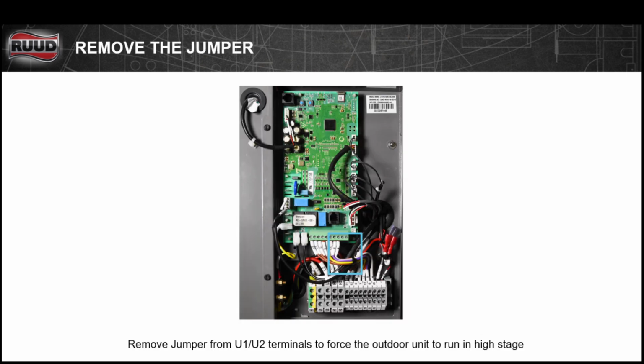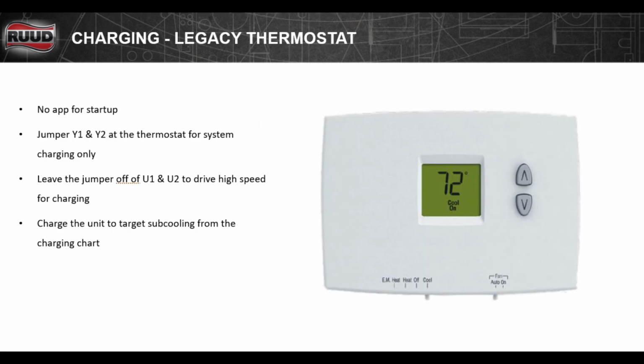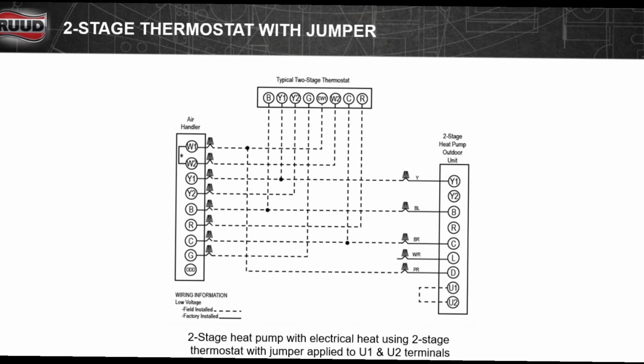We're going to remove the U1 and U2 jumper. Then we're going to jumper Y1 and Y2 at the air handler and the condenser in order to achieve 100%. Then we're going to use the charging chart at the condenser to charge the system correctly. Remember to reinstall the U1 and U2 jumper and remove Y2 from the condenser so that we can use the Ruud algorithm.